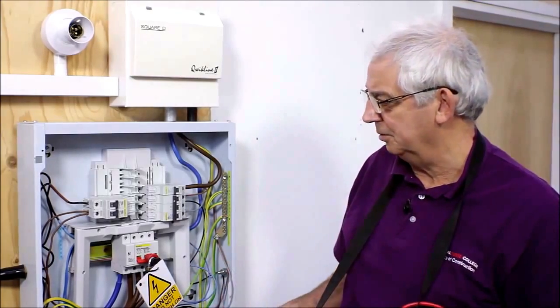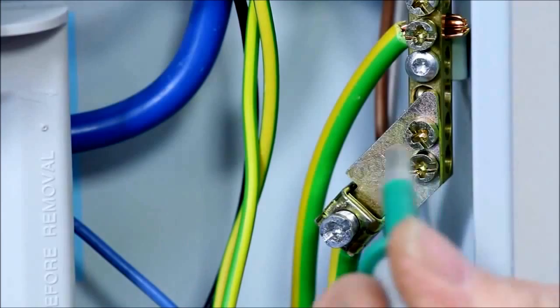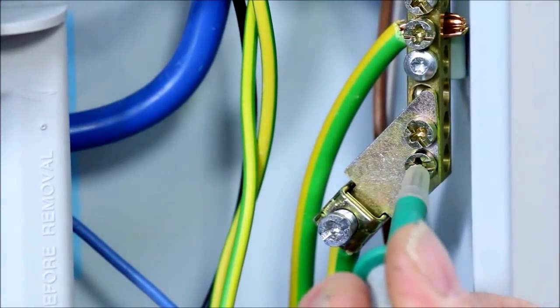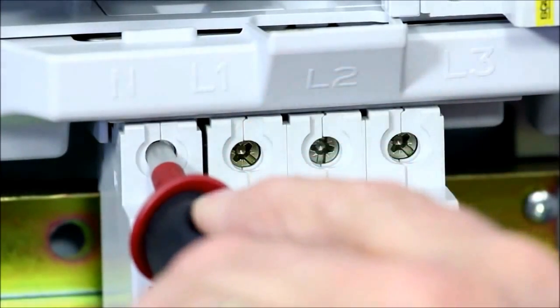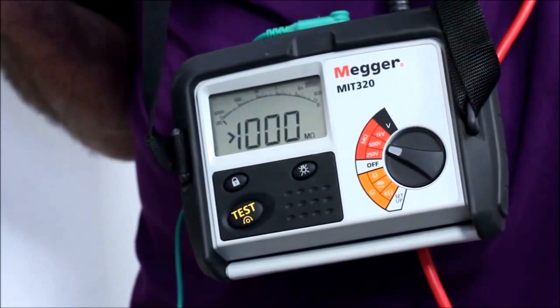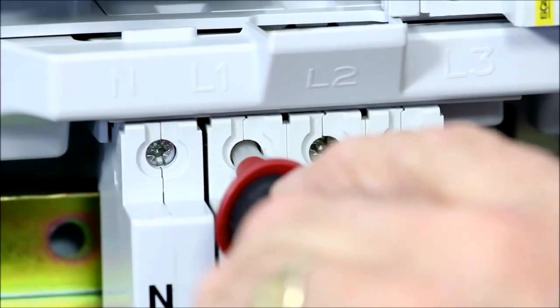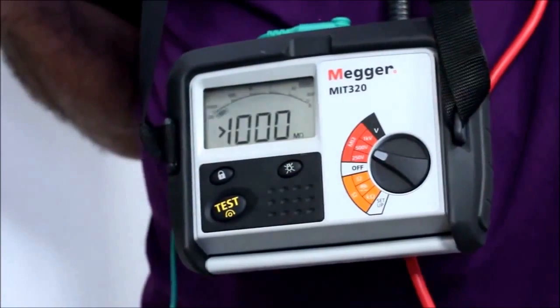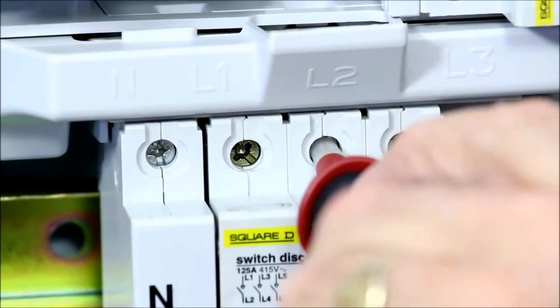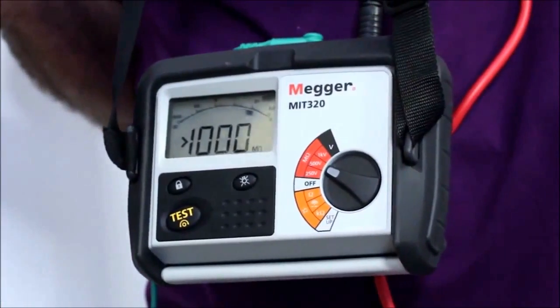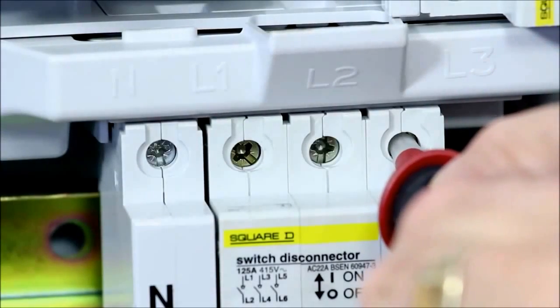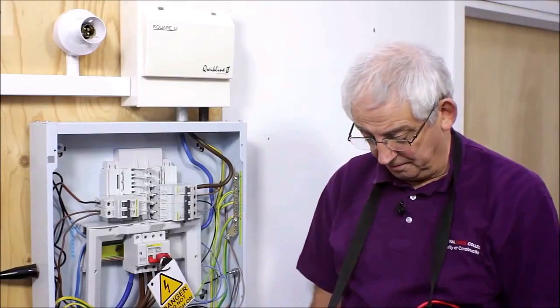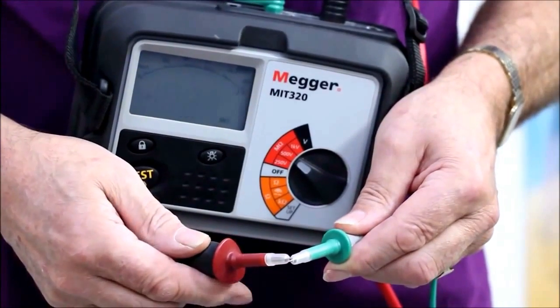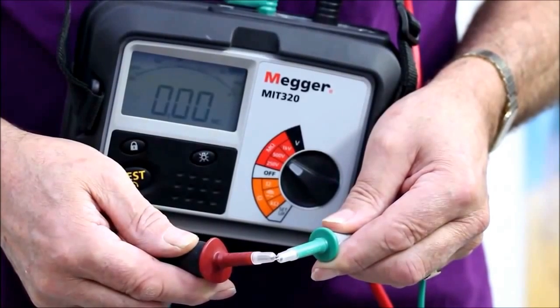The other test I need to do, of course, is between all live conductors and earth. So make sure the probe's secure onto an earth point, test between neutral and earth, should be over range. L1 to earth, again over range. L2 to earth, again over range. L3 to earth, again over range. Just to make sure the machine's still working, probes together, and I've got a reading of 0 again. And that's an insulation resistance test on a 3-phase installation.